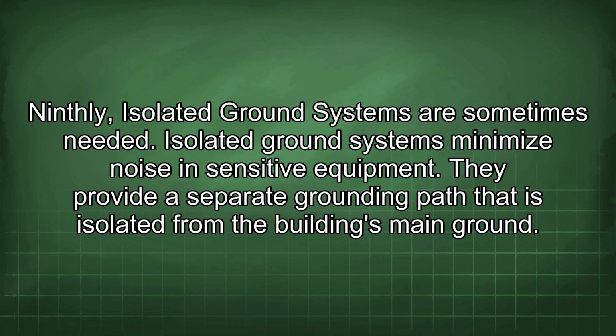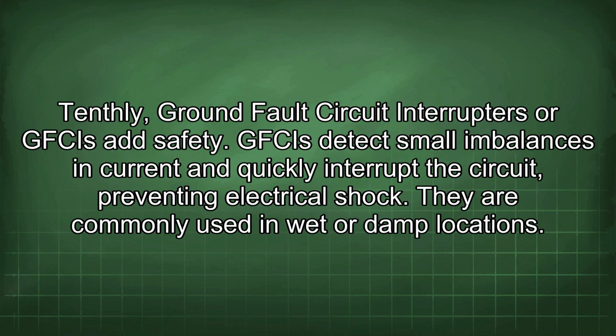Ninthly, isolated ground systems are sometimes needed. Isolated ground systems minimize noise in sensitive equipment. They provide a separate grounding path that is isolated from the building's main ground. Tenthly, ground fault circuit interrupters, or GFCIs, add safety. GFCIs detect small imbalances in current and quickly interrupt the circuit, preventing electrical shock. They are commonly used in wet or damp locations.